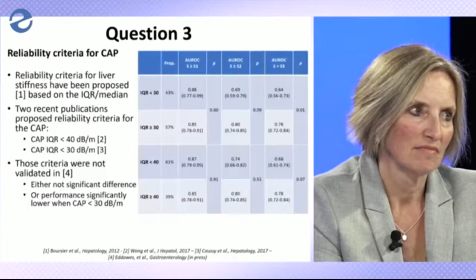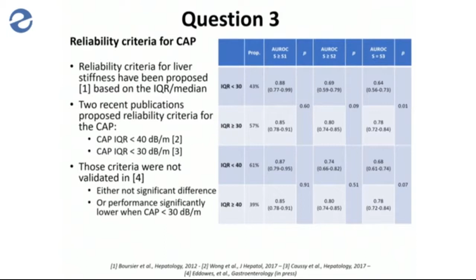We still have to take a look at that at the end of the exam. For the CAP, if you look at recent data published, evaluating the relevance of this IQR-based reliability criteria for CAP, they have tested the thresholds of 40 decibel per meter as an IQR and 30 decibel per meter. And if you look at the data, the diagnostic performance of the CAP versus histology, versus biopsy, is not different for examinations with IQR below 30 or higher than 30, and it's the same if you take the 40 decibel per meter IQR criteria. So our position for EchoSens is not to recommend anything for now as a quality criteria for CAP.